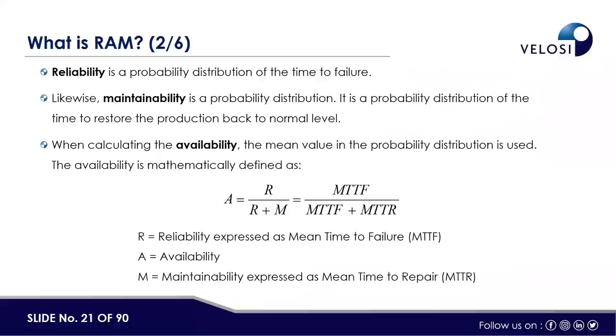In formal terms: A is availability, R is reliability expressed as mean time between failures — which could be in years or hours — and M is maintainability expressed as mean time to repair (MTTR), the time taken for repair. For example, if a pump goes out of order and the maintenance department takes two days to repair it, the MTTR for that pump is two days. Availability equals MTTF divided by (MTTF plus MTTR) — adding those two times gives the availability of the equipment or facility.